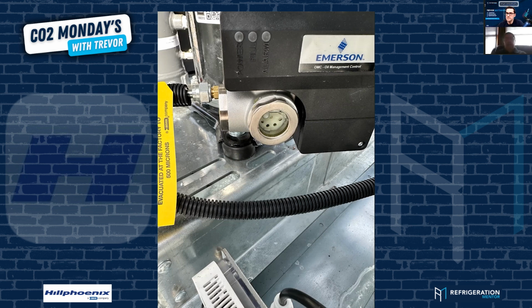We've got an inline 8mm bullet filter in the liquid line, the oil line from the separator to the reservoir, and from the reservoir to the compressors, to the actual header for the compressors. Take them apart. Don't be afraid to take them apart. Do the due diligence. Figure out why. If they're clean, if they're dirty, you can take them apart and clean them. It looks like a little porous rock when you take it apart, about the size of a thimble. You just got to isolate it properly, make sure there's no pressure in there, and then take it apart, take a look. This is our job. This is why we're mechanics, and this is just a small piece of what we need to do.